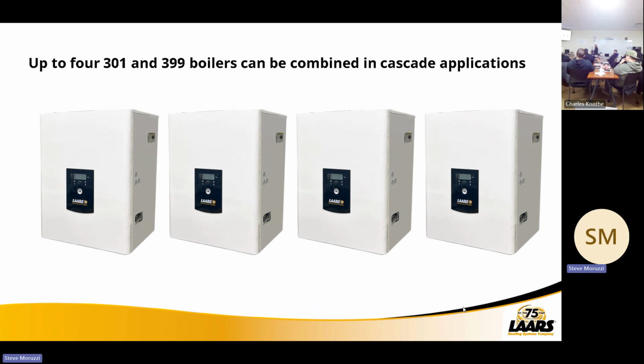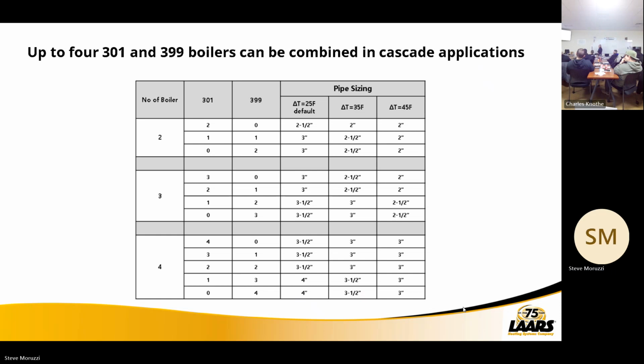And like I said, we can do 4 of these. We can mix and match them. And we're showing even here delta Ts and pipe size. So if I have 2 301s with a 25-degree delta, it's 2.5-inch pipe. Down here, the next column down, if I have 3 301s, a 25-degree delta would be 3-inch pipe, 35 would be 2.5, 45 would be 2. And if I mix and match these, so 2 301s and a single 399, 3-inch for a 25-degree delta, 2.5, et cetera. So we give you that information.